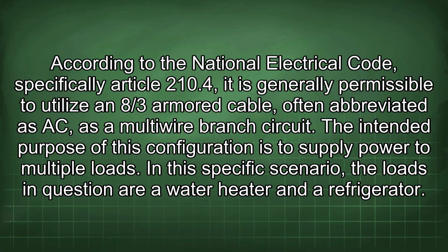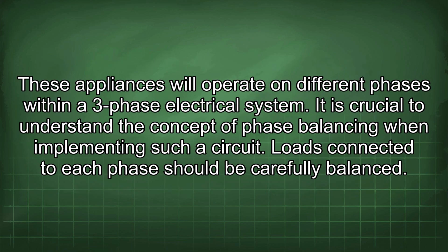According to the National Electrical Code, specifically Article 210.4, it is generally permissible to utilize an 8/3 armored cable, often abbreviated as AC, as a multi-wire branch circuit. The intended purpose of this configuration is to supply power to multiple loads. In this specific scenario, the loads in question are a water heater and a refrigerator. These appliances will operate on different phases within a three-phase electrical system.